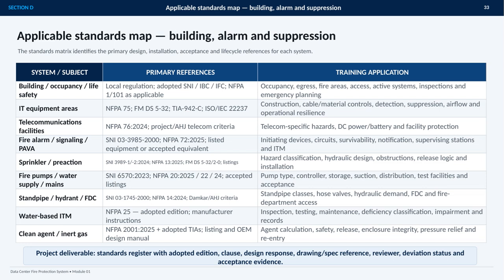Fire alarm and PAVA references address initiating devices, circuit survivability, notification, supervising stations, and ITM. Sprinkler, preaction, fire pump, standpipe, hydrant, and FDC references establish hydraulic demand, release logic, water supply, access, installation, and acceptance requirements. Water-based systems are then maintained through inspection, testing, deficiency management, impairment controls, and records. Clean agent and inert gas systems add agent calculations, enclosure integrity, pressure relief, release safety, and reentry controls.